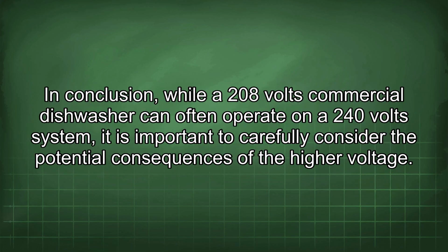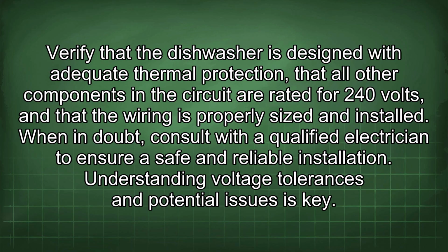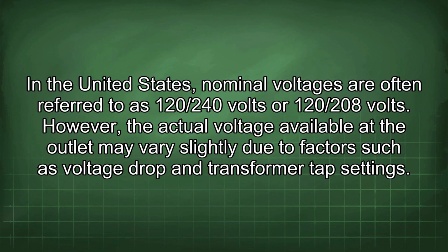In conclusion, while a 208 volts commercial dishwasher can often operate on a 240 volt system, it is important to carefully consider the potential consequences of the higher voltage. Verify that the dishwasher is designed with adequate thermal protection, that all other components in the circuit are rated for 240 volts, and that the wiring is properly sized and installed. When in doubt, consult with a qualified electrician to ensure a safe and reliable installation. Understanding voltage tolerances and potential issues is key. In the United States, nominal voltages are often referred to as 120/240 volts or 120/208 volts.